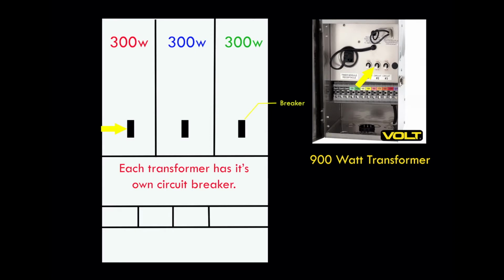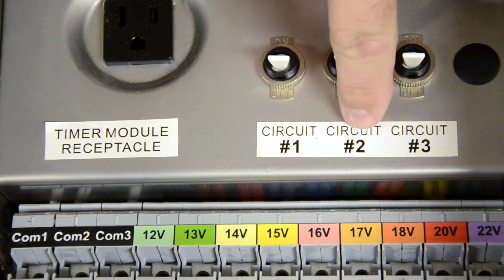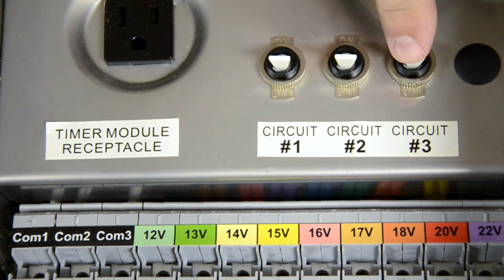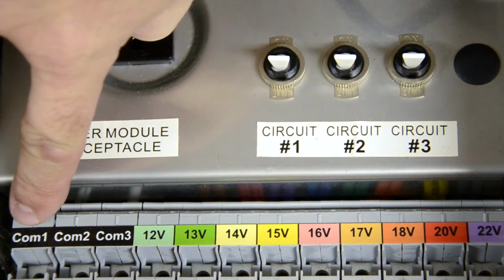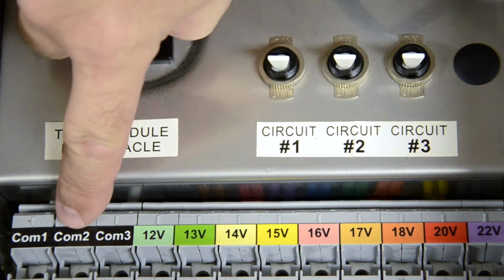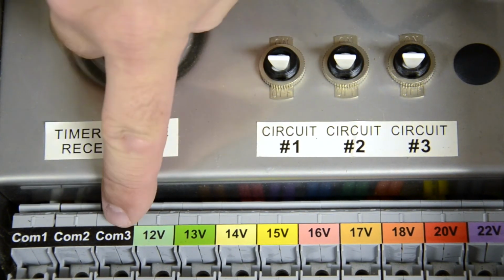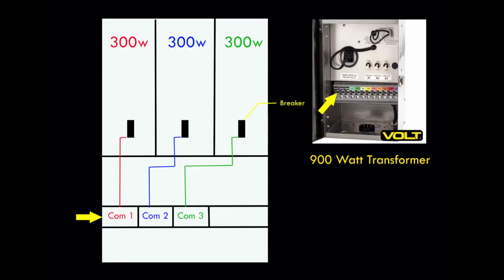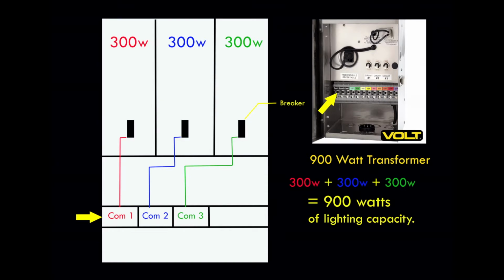Each of these 300 watt transformers is also individually protected with its own circuit breaker. Each internal transformer will also have its own associated common, shown down below in the screw terminals. Looking inside this transformer, we can see the layout and how the circuits refer to each of the commons. The switches will refer back down to common 1, to circuit 1, common 2, to circuit 2, common 3 to circuit 3. Each one of these internal transformers is wired to its associated common. By stacking all 3 of these 300 watt transformers side by side, that gives us 900 watts of usable capacity for lighting.